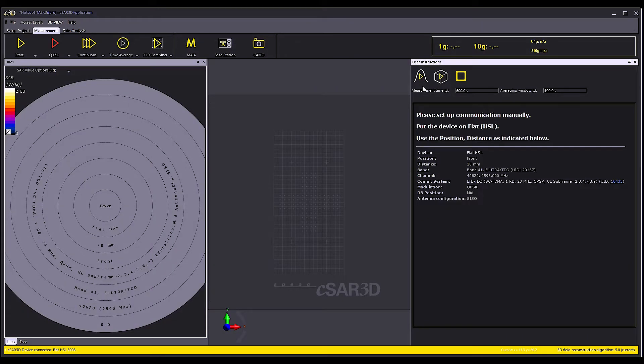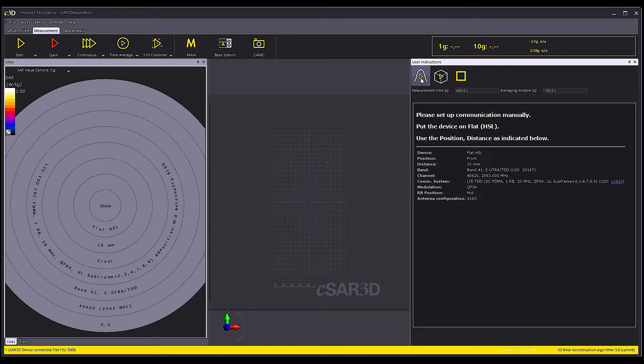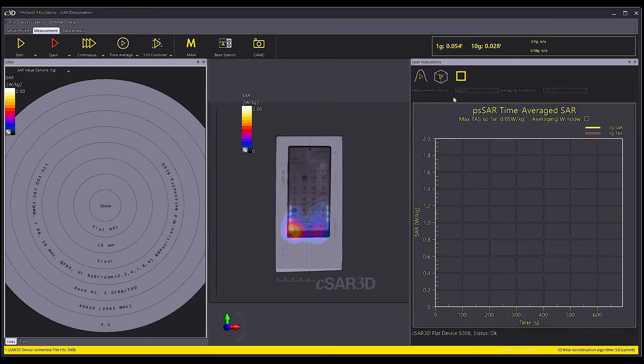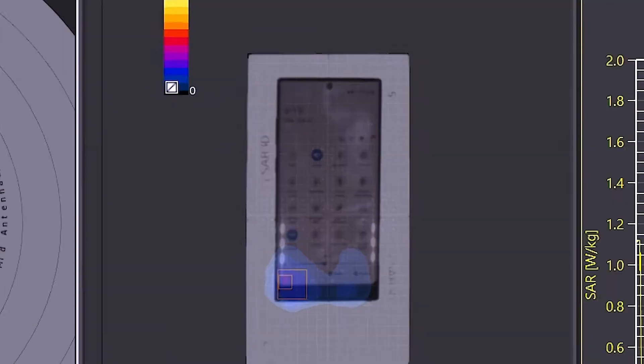I then start the PSAR time averaged TAS measurement with this button here. I enable TAS on the phone with the hotspot mode. And now look at the plot.